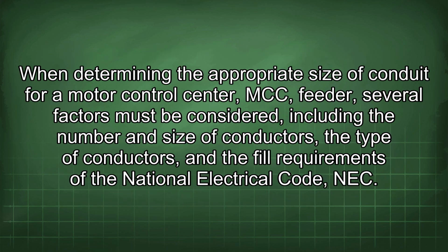safety. When determining the appropriate size of conduit for a motor control center (MCC) feeder, several factors must be considered, including the number and size of conductors, the type of conductors, and the fill requirements of the National Electrical Code (NEC).